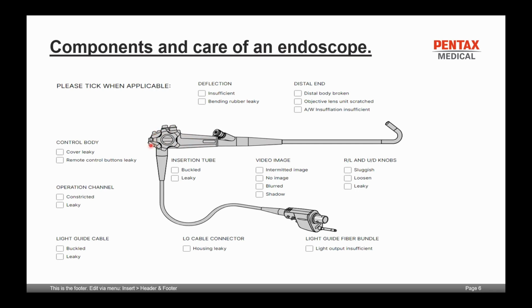You've got remote control buttons, which you can assign to do different functionalities for the endoscope. Another root brace leads to your umbilical cord or light guide long cable, which leads to your electrical or PVE connector. On your PVE connector, you've got your suction nipple, a grounding port to ground the endoscope while doing electrosurgical work. You've got your electrical connector, an air water connector on the other side, and your light guide prong assembly.